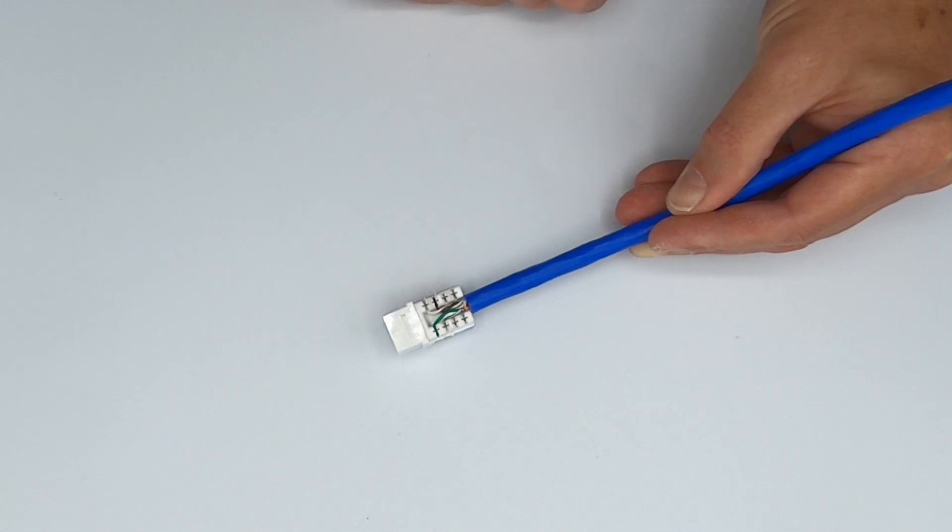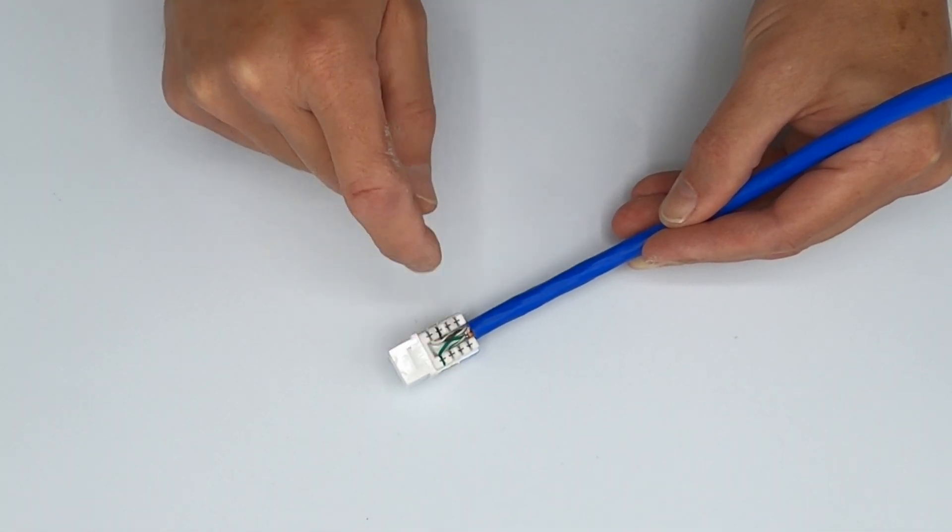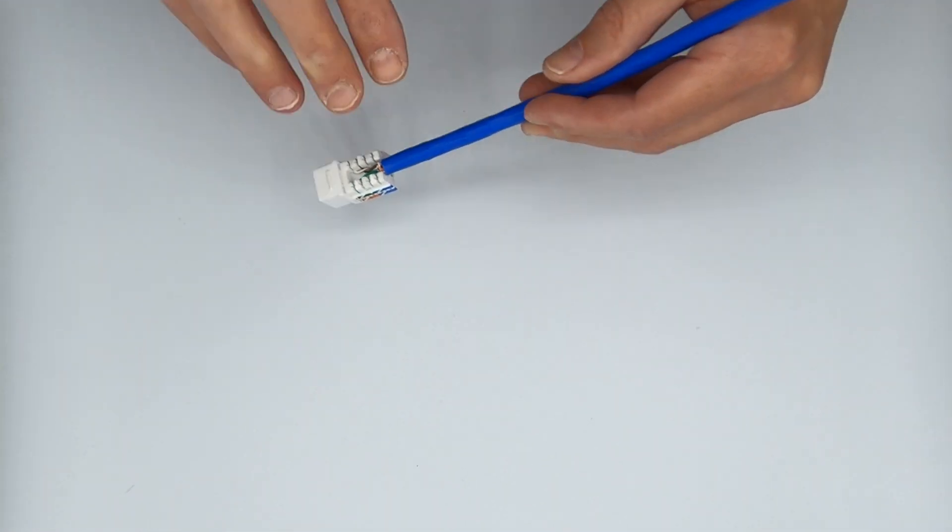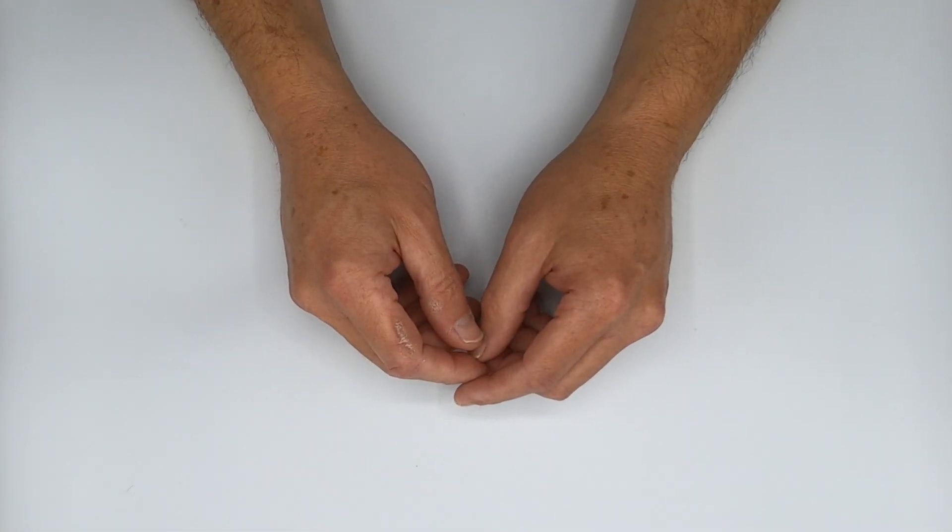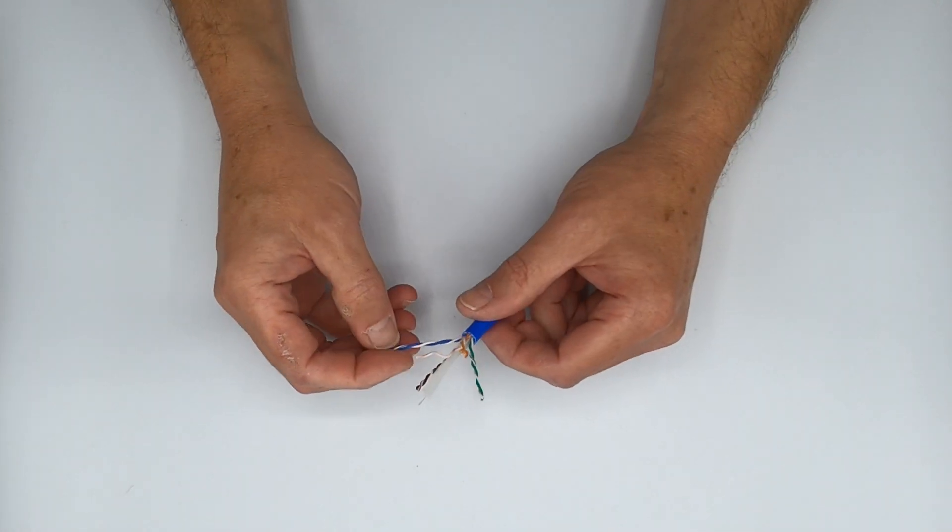But as you can see from where they actually make contact with the metal prongs in there between these slots to where the last twist is in that conductor pair, it's above one half inch. So this particular jack is not going to perform to specification, if at all.